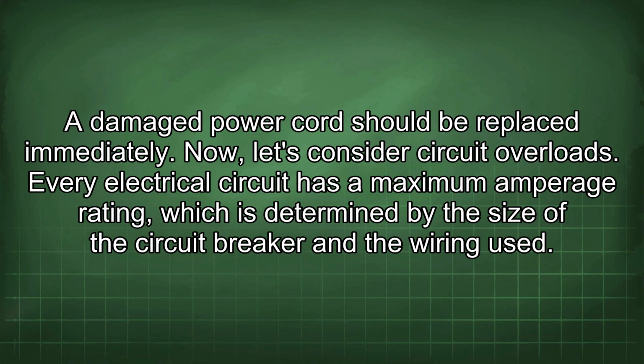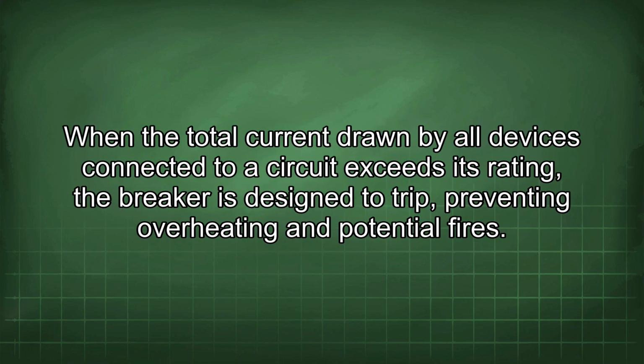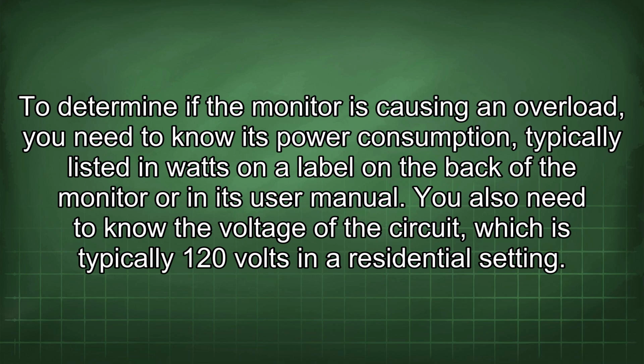Now let's consider circuit overloads. Every electrical circuit has a maximum amperage rating, which is determined by the size of the circuit breaker and the wiring used. When the total current drawn by all devices connected to a circuit exceeds its rating, the breaker is designed to trip, preventing overheating and potential fires. To determine if the monitor is causing an overload, you need to know its power consumption, typically listed in watts on a label on the back of the monitor or in its user manual.